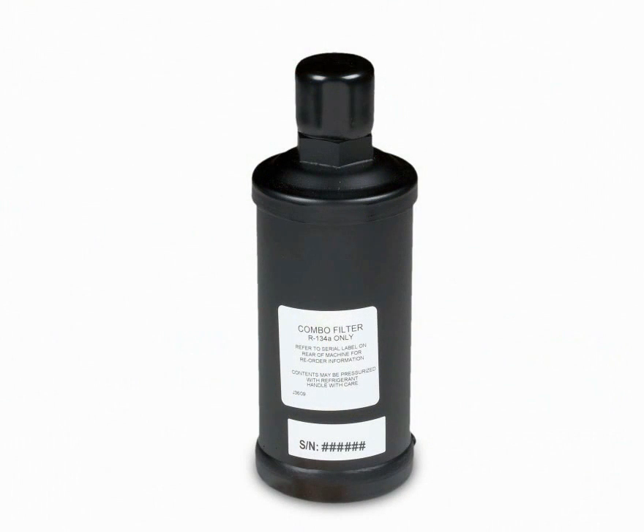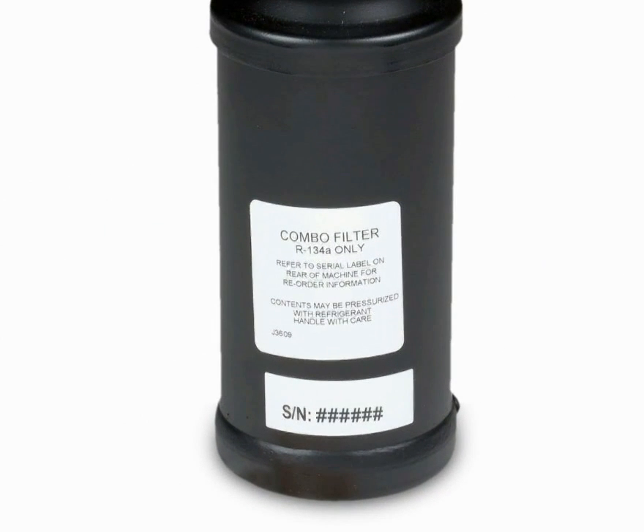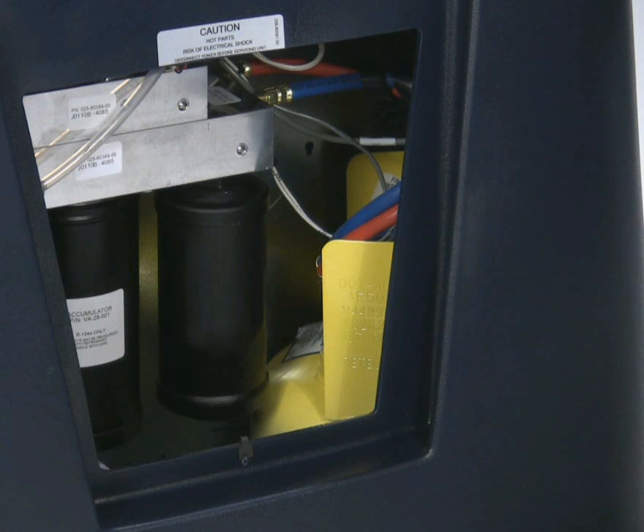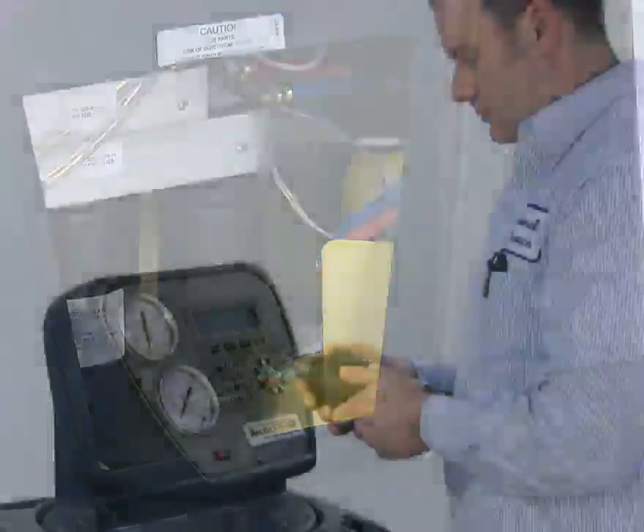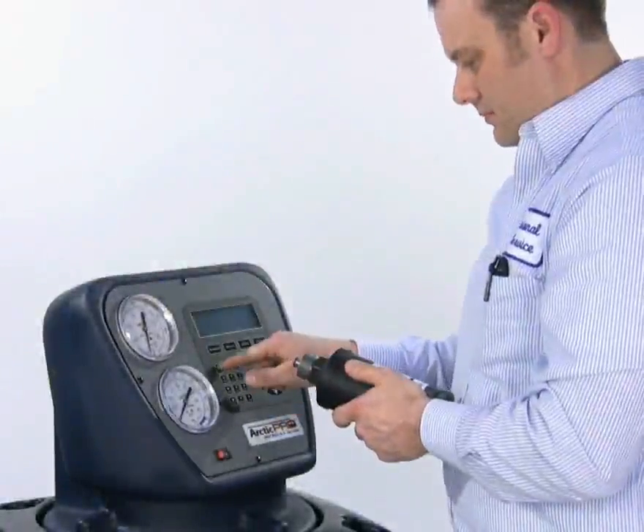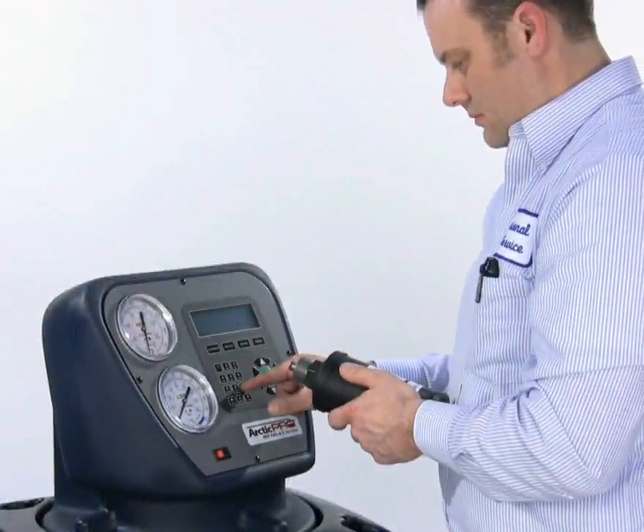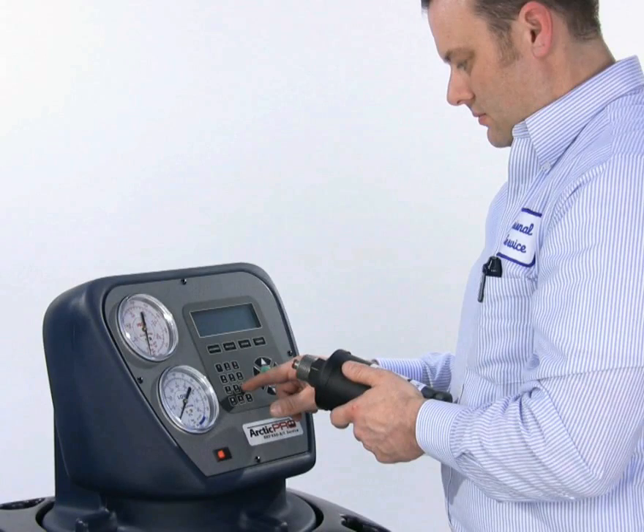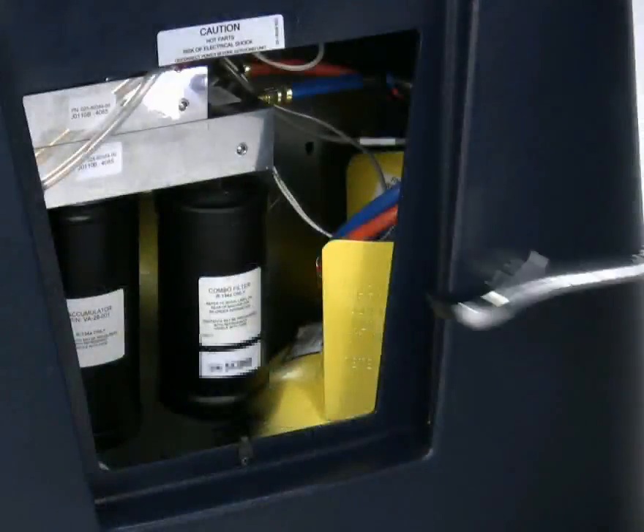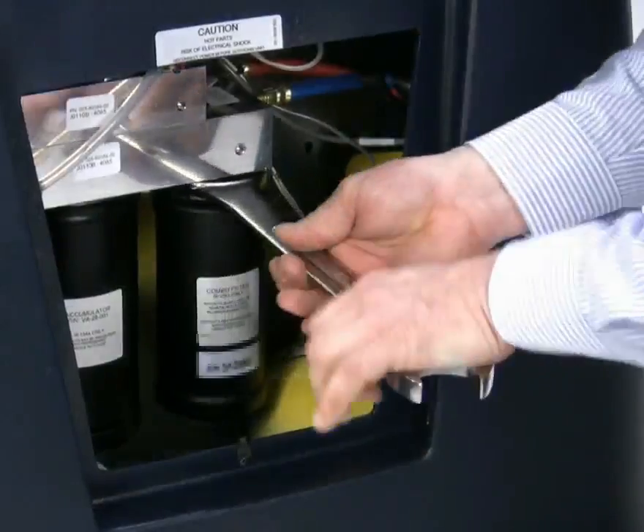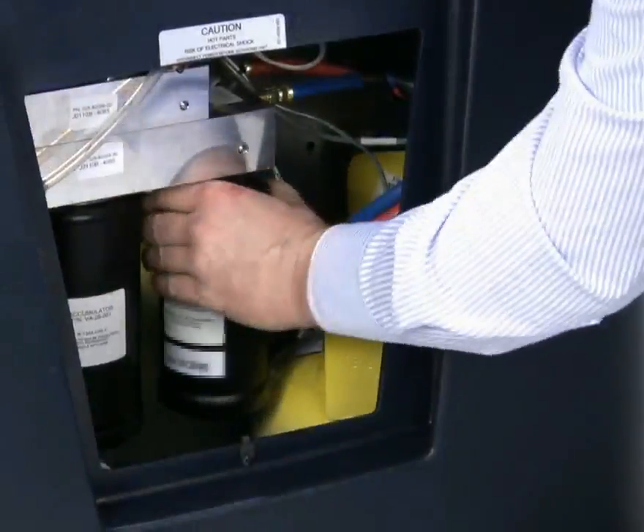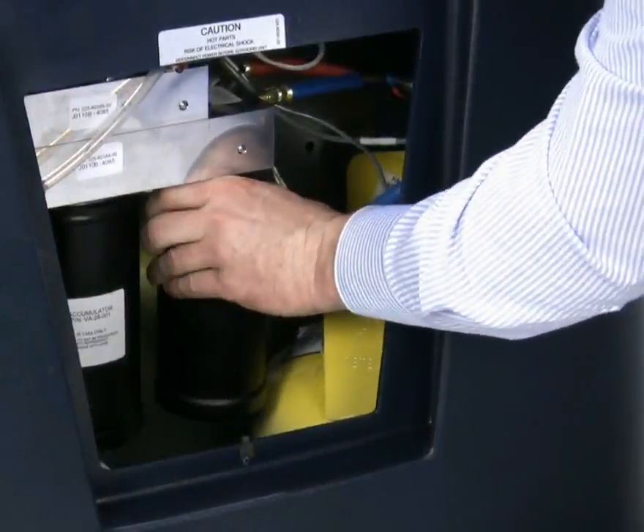A serial number is printed on the label attached to the new filter. Make sure you record this number to reactivate your RHS980, because it may not be readily visible when it is screwed into place on the block manifold assembly. If you prefer, you can enter the new filter code into the processor using the keypad before you actually remove the used filter. Now, using your open-ended wrench, engage the hex shoulder and carefully apply pressure to unscrew the filter from the manifold block assembly.